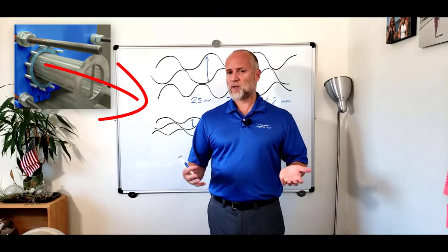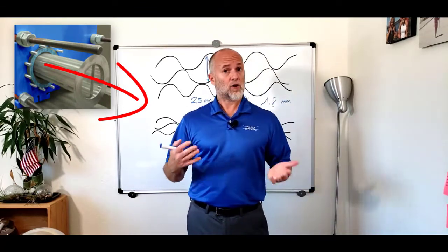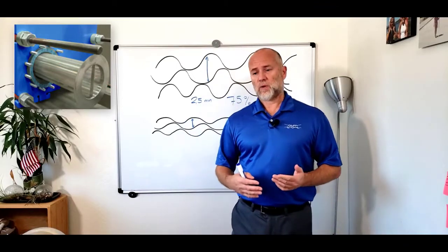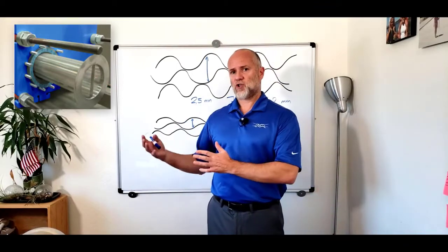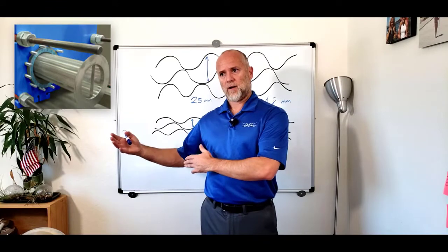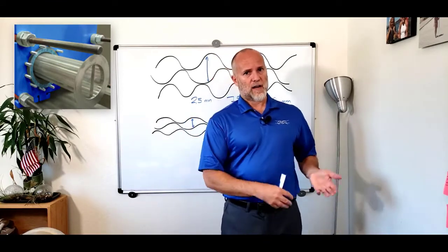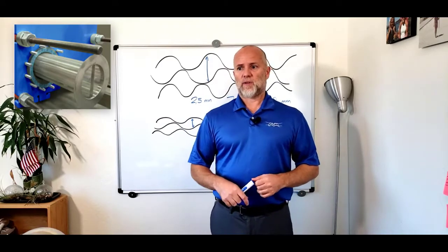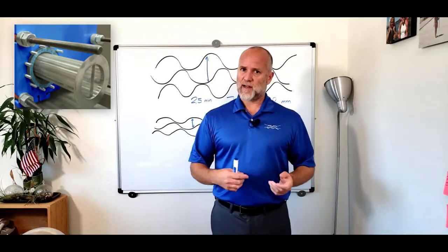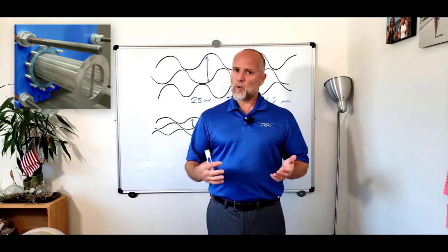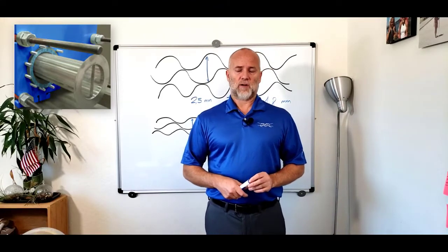So it's always a good idea. They are not mutually exclusive. It could be a good idea to have a larger mesh in a strainer before the heat exchanger, and then you can also have a port filter in the heat exchanger. The pressure drop that you have adding a port filter is negligible, so we always suggest, if you have a chance, to include the port filter in your initial design.